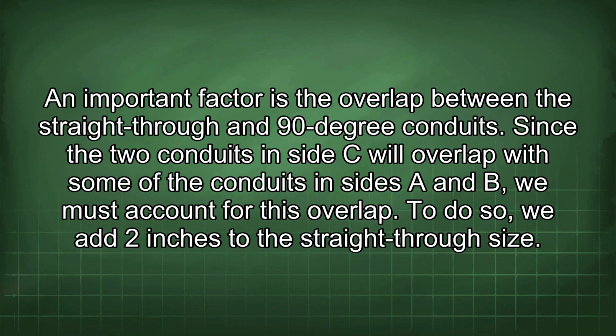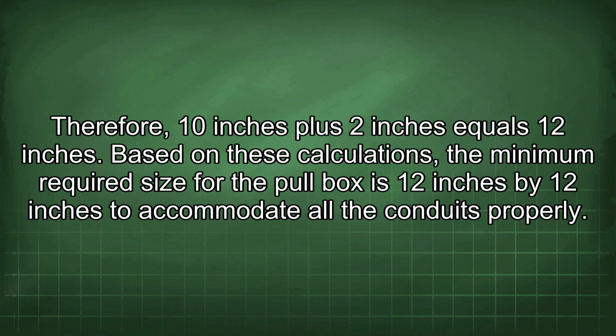An important factor is the overlap between the straight-through and 90-degree conduits. Since the 2 conduits in side C will overlap with some of the conduits in sides A and B, we must account for this overlap. To do so, we add 2 inches to the straight-through size. Therefore, 10 inches plus 2 inches equals 12 inches.